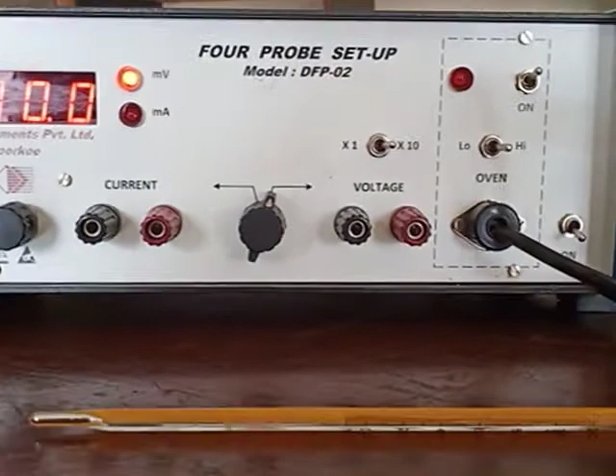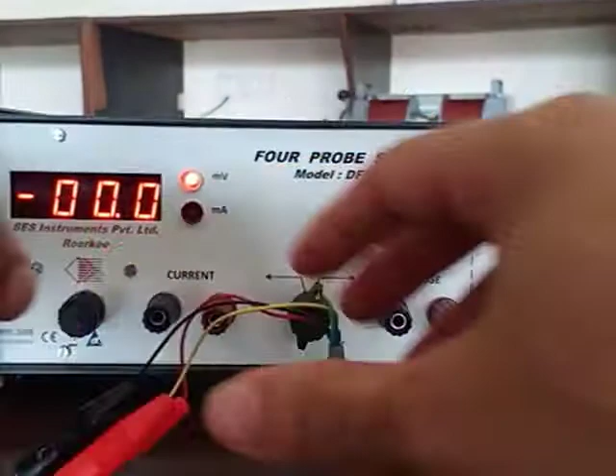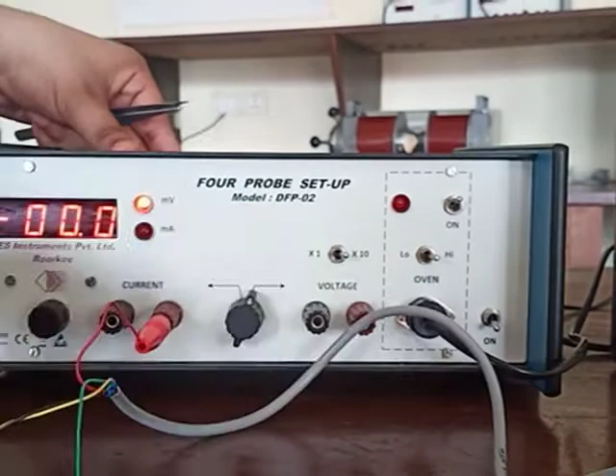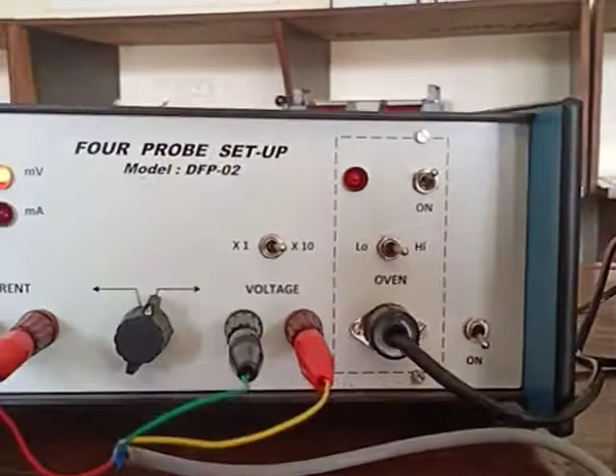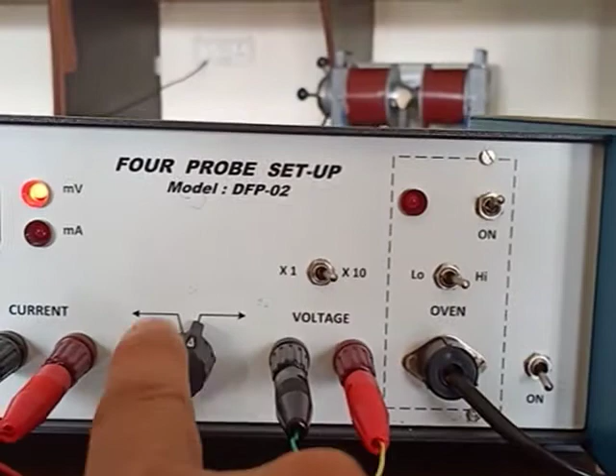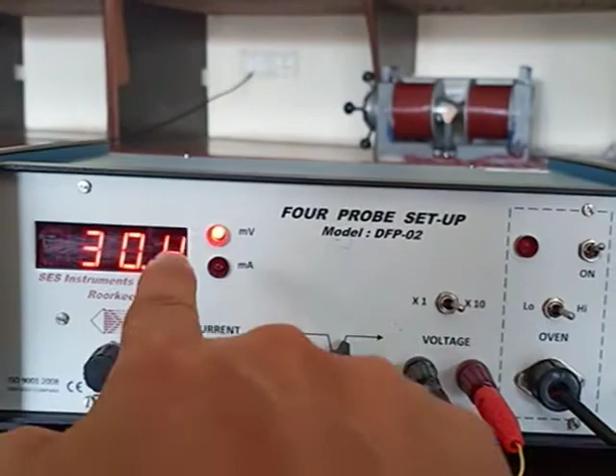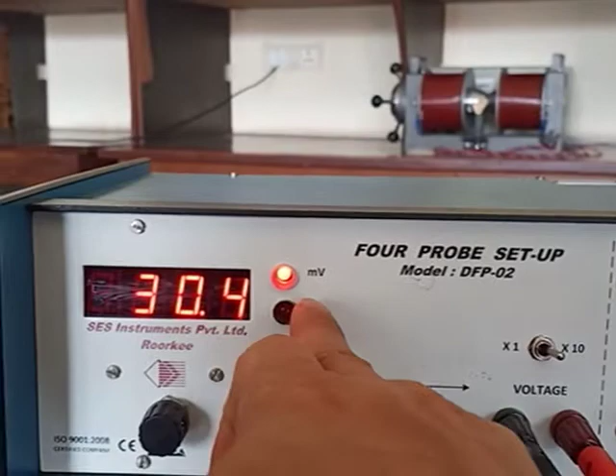You can see on the four probe setup there are some points given. These 2 points are for the connection of the current, and these 2 points are for the connection of the voltage. In between them there is a knob. You can select what you want to measure or display on this four probe setup. This time the knob is towards the voltage, so it is giving the voltage in millivolts.